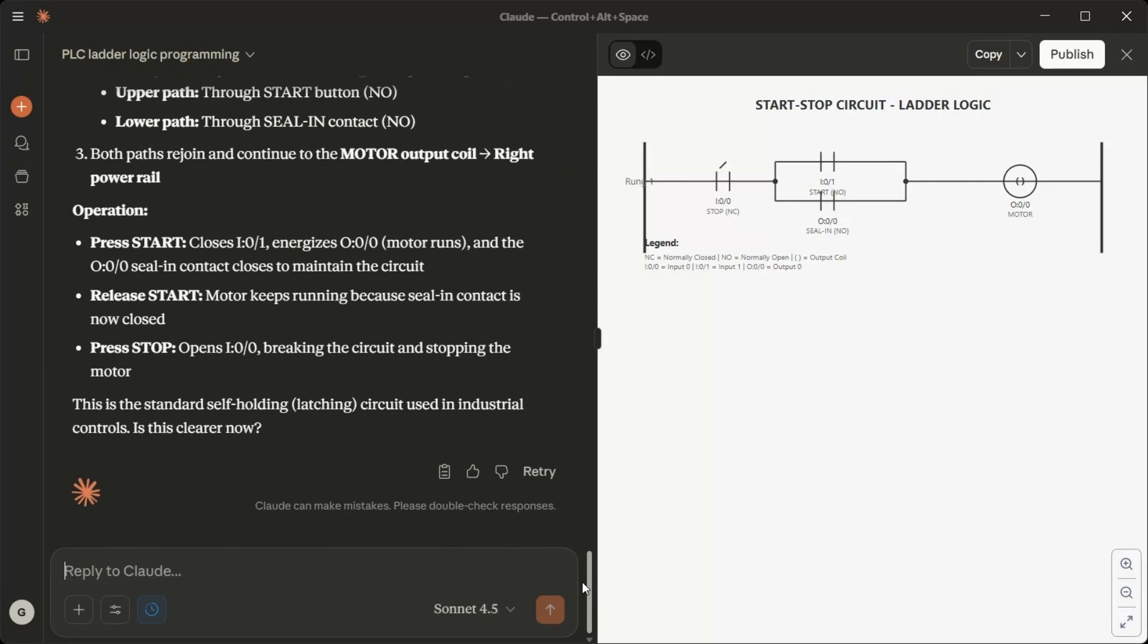Operation: Press start closes I0/1, energizes O0/0, motor runs, and the O0/0 seal in contact closes to maintain the circuit. Release start, motor keeps running because seal in contact is now closed. Press stop, opens I0/0, breaking the circuit and stopping the motor. This is the standard self-holding latching circuit used in industrial controls. Is this clear now?